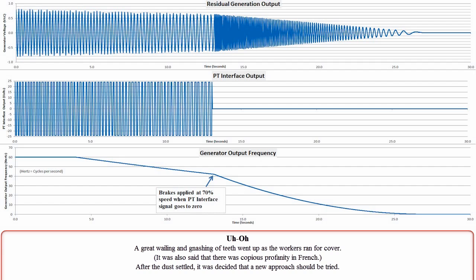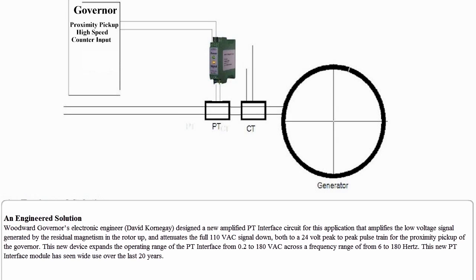After the dust settled, it was decided that a new approach should be tried. Woodward Governor's electronic engineer, Dave Cornegay, designed a new amplified PT interface circuit for this application that amplifies the low voltage signal generated by the residual magnetism in the rotor up and attenuates the full 110 volts AC signal down, both to a 24 volt peak-to-peak pulse train for the proximity pickup of the governor. This new device expands the operating range of the PT interface from 0.2 to 180 volts AC across a frequency range of from 6 to 180 Hz.